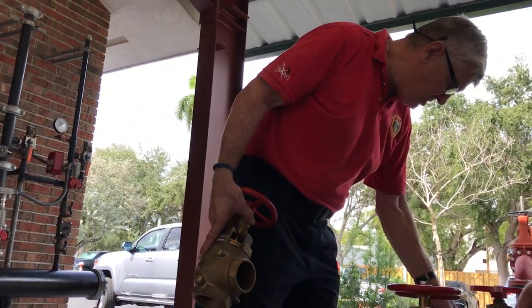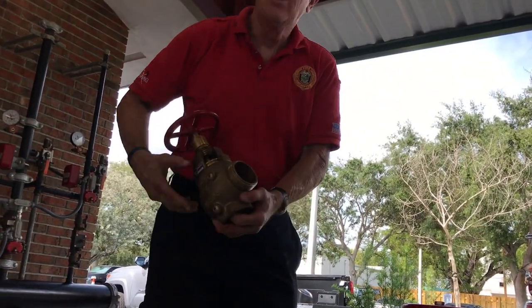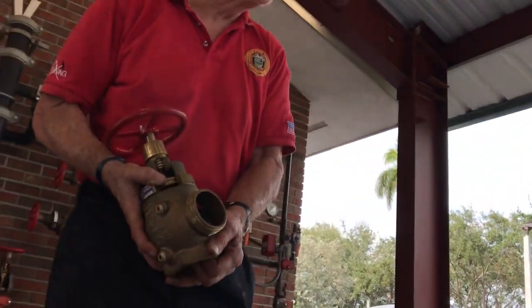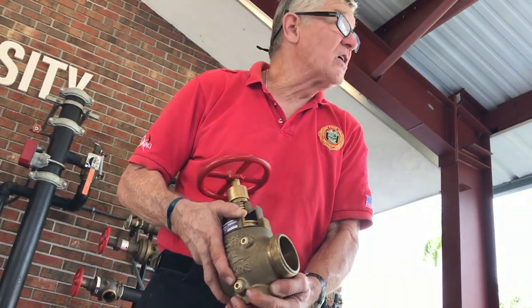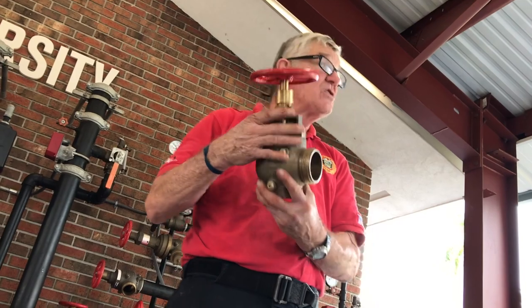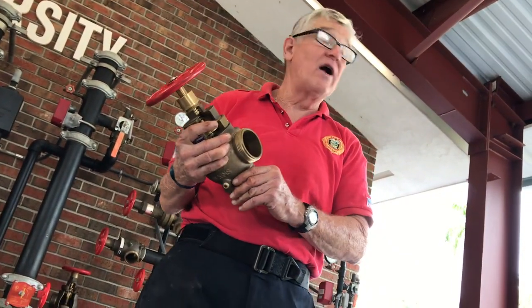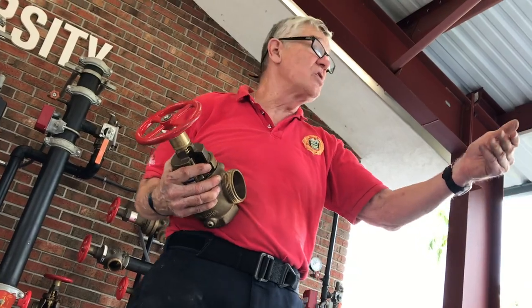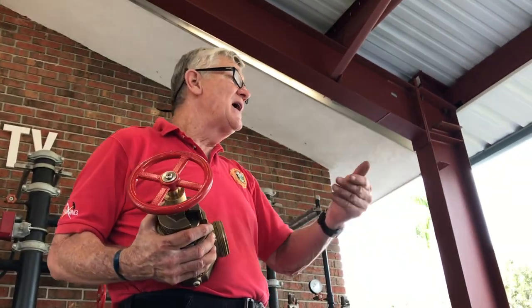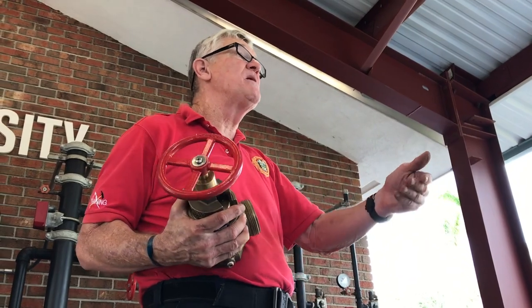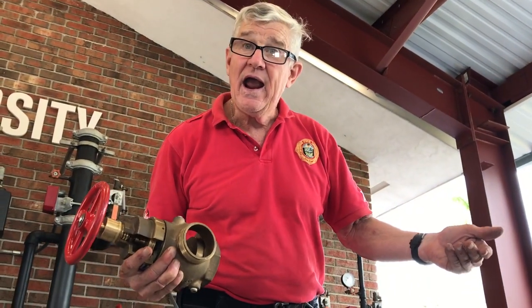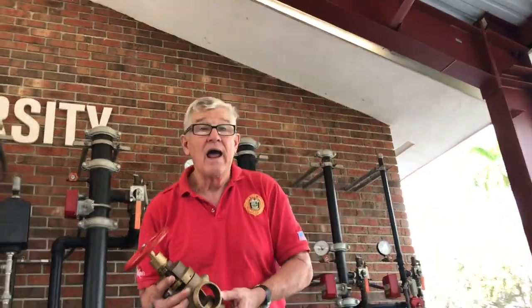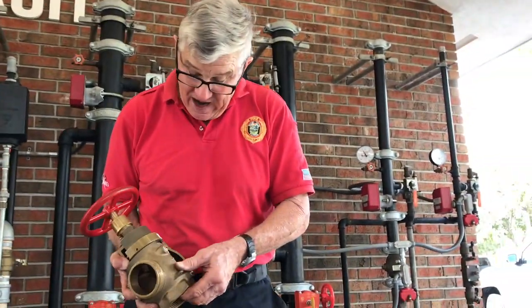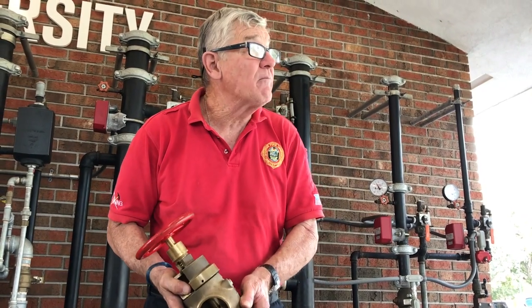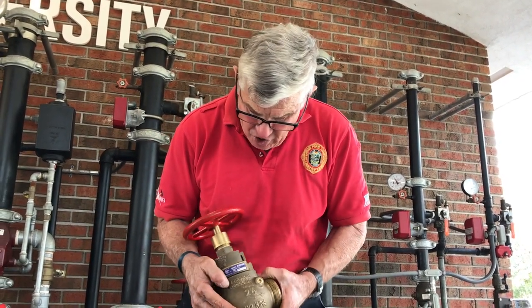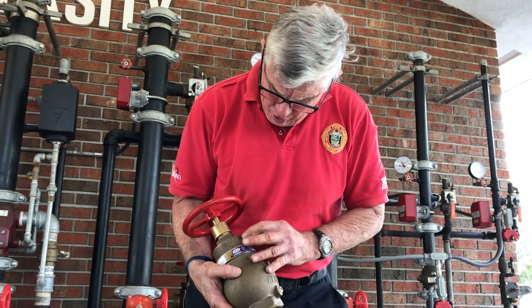Now, there are two basic types of pressure reducing valves. This one is set at the factory. It's a factory set valve. When it comes to the job site, it will specify what the floor is and what the inlet pressure should be, the static and residual inlet and outlet pressures. The outlet pressure has to be between 100 and 175 PSI. So this is factory set, and each manufacturer has its own designation for pressure ranges.